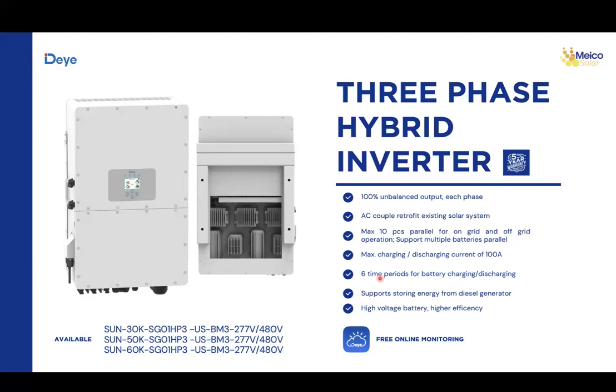Same thing as with the single phase solution. You can do time of use, peak shaving, and put it with a prior AC coupled system with microinverters or whatever AC coupling the customer has. And as well, it can support the customer's genset. It can turn that genset on and off completely and control it with the inverter. In this case, it is not a low voltage battery, but all the three phase hybrid inverters work with high voltage batteries.